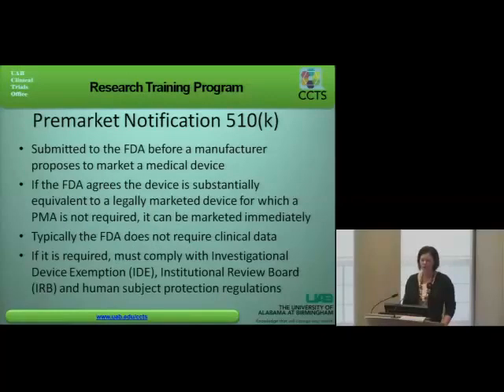So I mentioned the pre-market notification 510K. This is one route that a device can go for approval to be marketed. It's submitted to the FDA before a manufacturer proposes to market a medical device. If the FDA agrees the device is substantially equivalent, meaning it's very similar to something on the market, if it is substantially equivalent to a legally marketed device for which a PMA is not required, it can be marketed immediately. Typically, the FDA does not require any clinical data for this type of submission process, but if it is required, it must comply with the IDE, IRB, and human subject protection regulations.